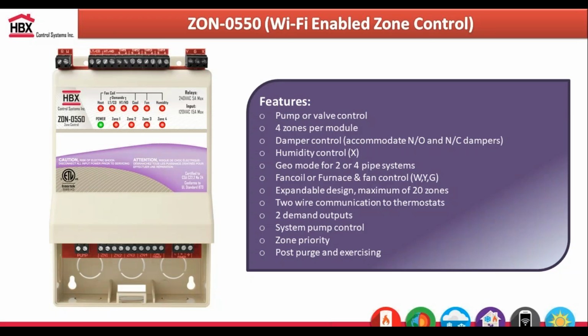So the Zone 550 can do zone pumps, zone valves, and it can also do forced air motorized dampers as well. So it can be used for radiant applications, or for forced air, like a furnace or air conditioner with 2 or 3 or 4 zone dampers. Or you can use a combination of radiant and forced air all in one HVAC zone controller. Typically, a customer may have 2 or 3 in-floor zones, but they have a backup furnace or a fan coil used as second stage heating or cooling, and they want to control that with a damper. You can accommodate that all through the Zone 550.